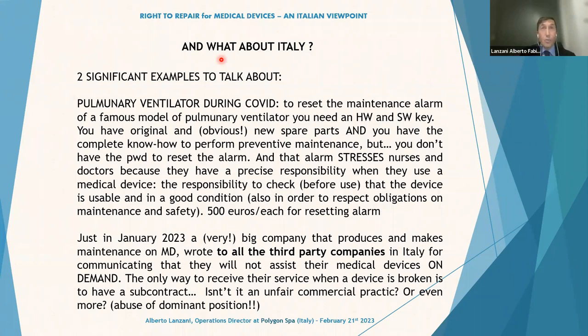In that situation, when you think you'll find collaboration from everybody, the manufacturer told us they wanted 500 euros per ventilator for resetting the alarm. We had to call them, obviously. I spent some thousands, some dozens of thousands of euros just to have the alarm reset, and they put on their intervention document that the maintenance was okay and that they had already reset the alarm. This is not acceptable, in my opinion.